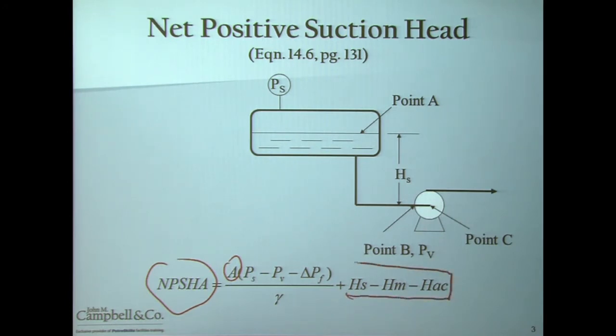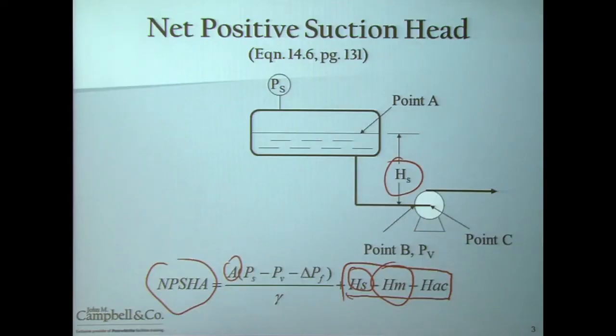To that, we add various factors. H sub S is the only positive term in this equation, which is the height of the liquid above the center point of the pump. We subtract a safety margin, and if you're dealing with a positive displacement pump, we also subtract an acceleration head factor. If you have a bubble point liquid, you'll be able to fairly quickly determine your net positive suction head available.